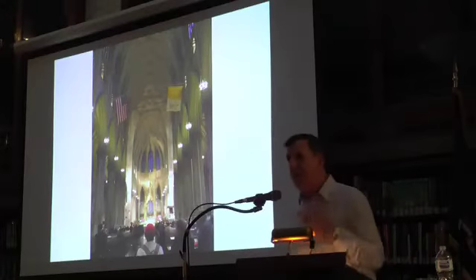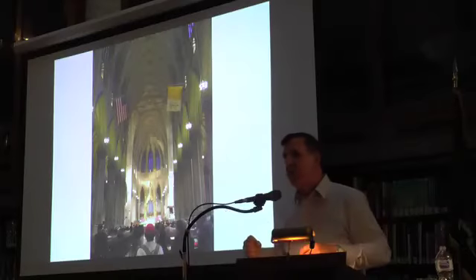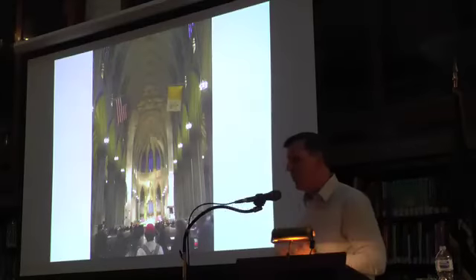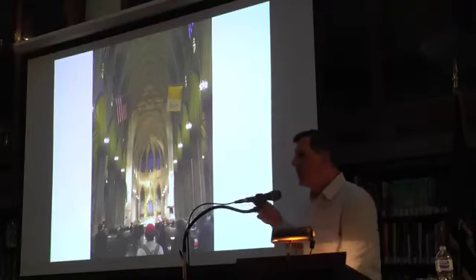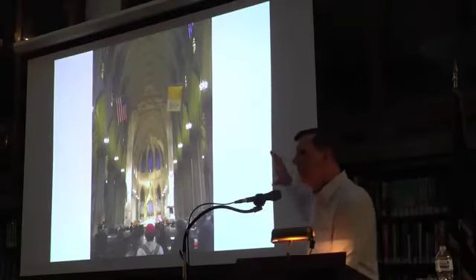So what they did back then, when they were heating buildings like this, cathedrals and government buildings and high spaces like this, is they would put in radiation that would, first of all, heat people, because radiators radiate about 40% of their energy and 60% is by convection. But they would set it up undersized so that the convective currents would rise up and stop. So it becomes like the atmosphere.